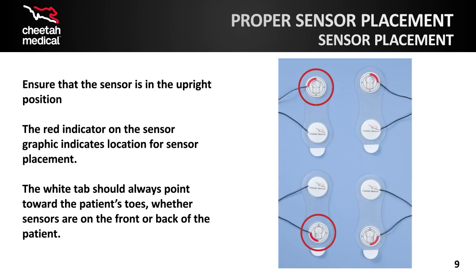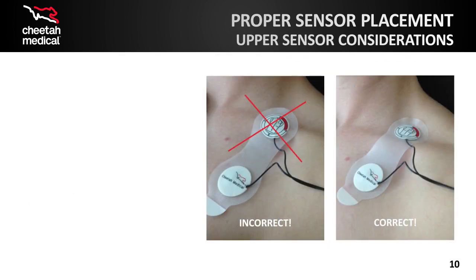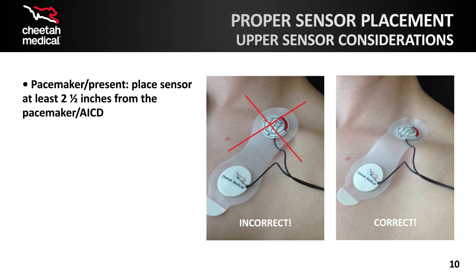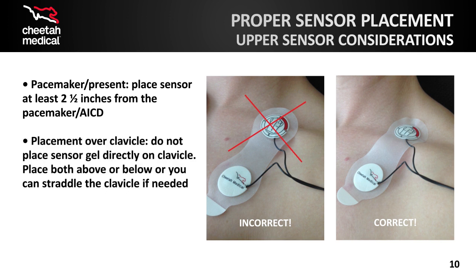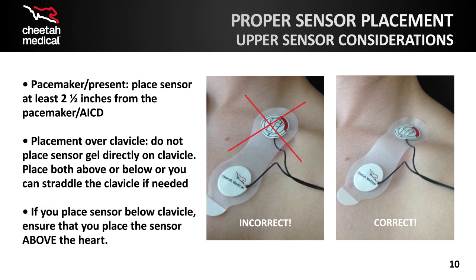As mentioned previously, there is a red indicator located on each sensor which directs proper sensor location. Always ensure the sensor is in the upright position with the small white tab pointing toward the patient's toes. For application of the upper set of sensors, please consider the following. Pacemaker AICD present. Place the sensor at least 2.5 to 3 inches from the pacemaker AICD. Placement over clavicle. Do not place sensor gel directly on the clavicle. Place both above or below, or you can straddle the clavicle if needed. If you place the sensor below the clavicle, ensure that you place the sensor above the heart. The sensor needs to be above the aortic arch, since Starling SV measures flow in the aortic arch.